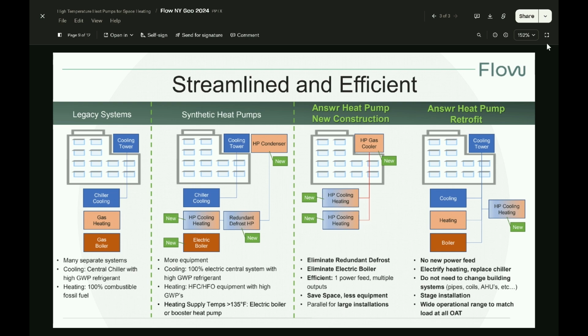If we can simplify that down into more of a centralized boiler plant that can share and optimize all that, now we can reduce things like defrost and air side. We can replace electric boilers. We can do low temperature cooling for those wells that have minimal glycol or antifreeze in them. Aquifer exchanges are now possible because you can do that without contaminating the groundwater source, since it's just above freezing.